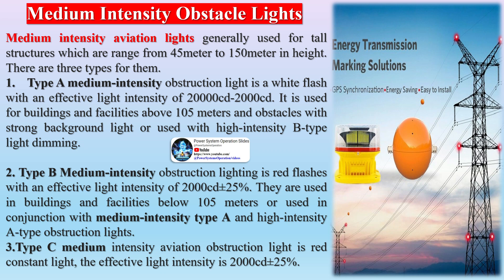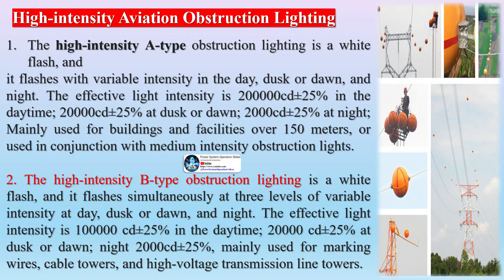Medium-intensity aviation obstruction lights — in FAA standard, the L864 obstruction light flashes red light, while the L865 type is white flashing. They are mainly used for obstacles ranging from 105 meters to 150 meters in height.